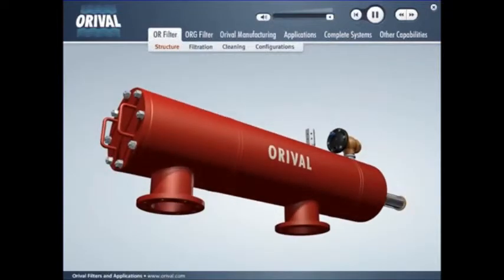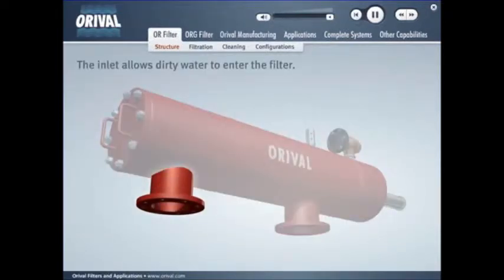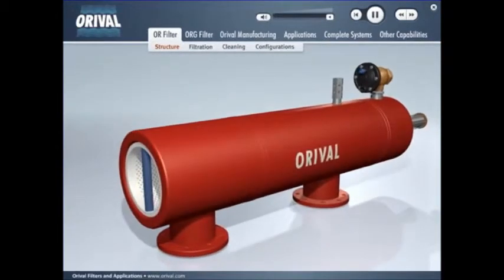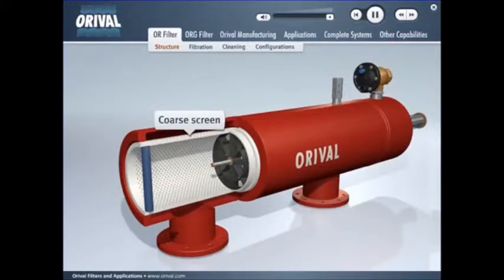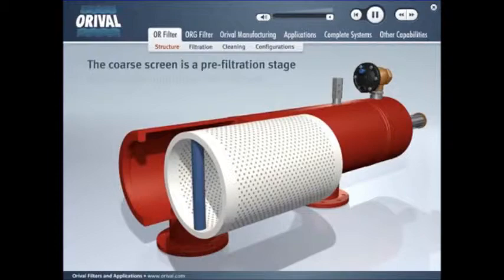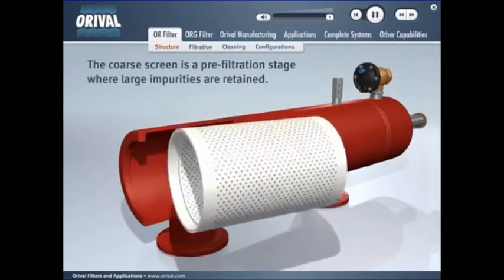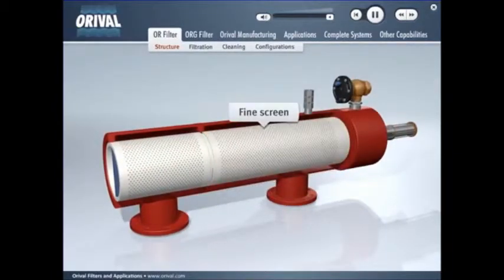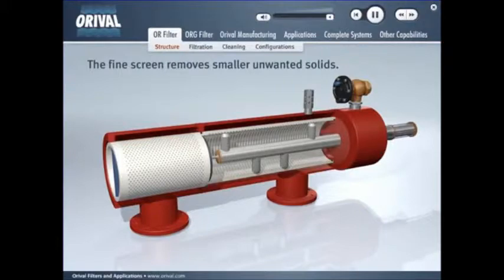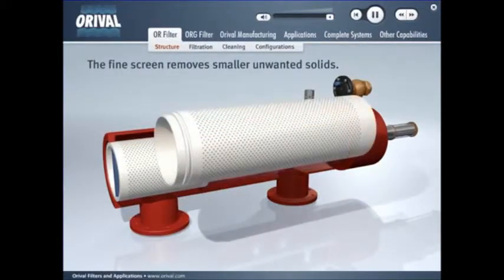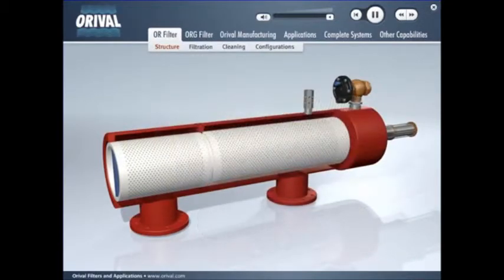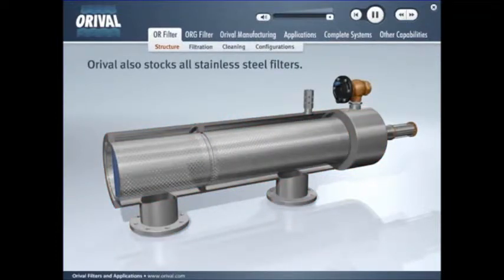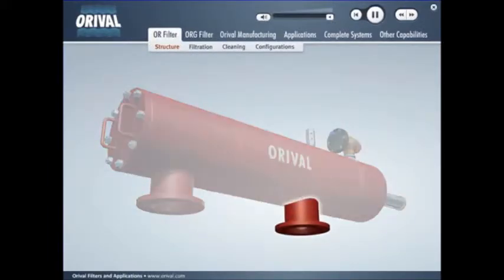The inlet allows dirty water to enter the filter. The coarse screen is a pre-filtration stage where large impurities are retained. The fine screen removes smaller unwanted solids. The standard screen is constructed of rugged PVC with a fine weave wire mesh of stainless steel inside. An all stainless steel multi-layer sintered screen is also available. Orival also stocks all stainless steel filters. The outlet allows cleaned water to exit the filter.